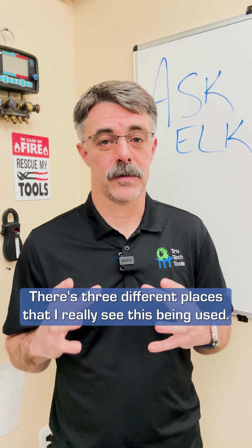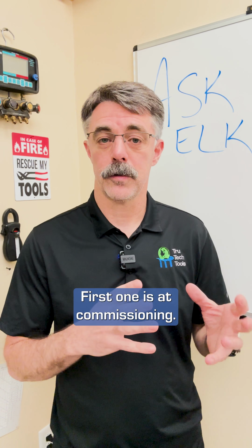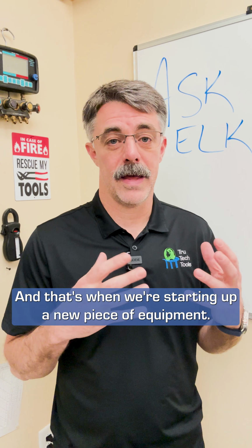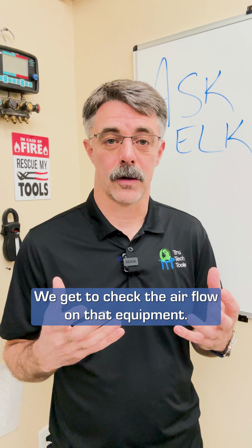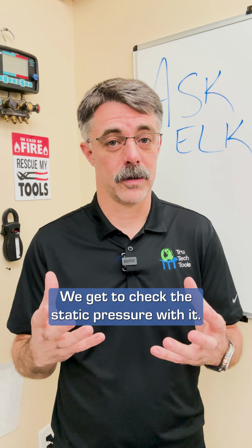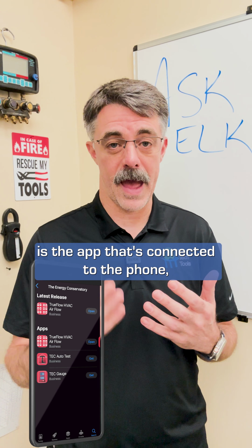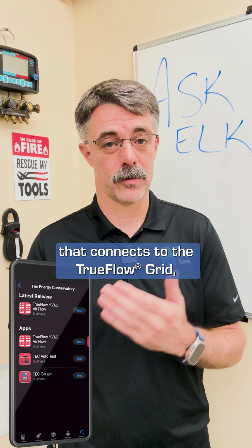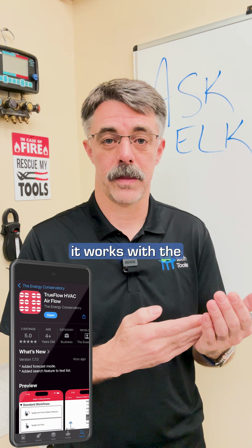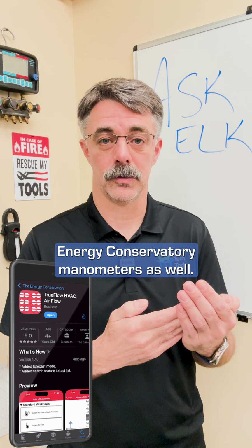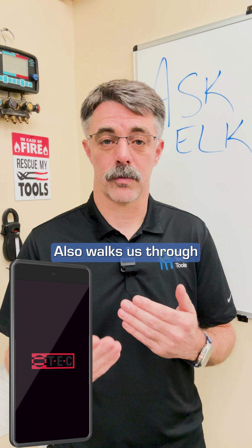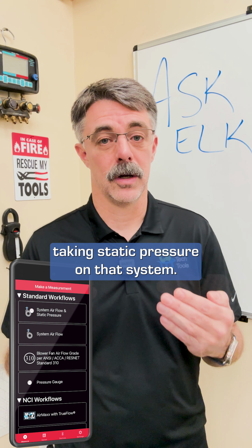There's three different places that I really see this being used. First is at commissioning, when we're starting up a new piece of equipment. We get to check the airflow on that equipment and check the static pressure, because the app that connects to the phone and to the TrueFlow grid also works with Energy Conservatory manometers and walks us through taking static pressure on that system.